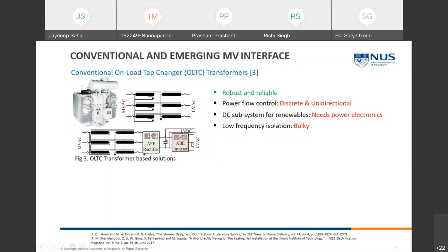Coming to the conventional strategy, where you use on-load tap changer transformers, you would usually have a discrete control over the voltage and thus the reactive power. One of the very well-known things is that they are quite robust and reliable. The power flow control is disadvantageous because it is discrete and unidirectional. Another disadvantage is that because of the low frequency isolation, it is quite bulky and would take quite a lot of floor space. Now, if you need to have a DC subsystem as shown here, you anyway need power electronics, right? So even if you have a low frequency transformer, you need a back-to-back converter system so that you can take out a DC bus.